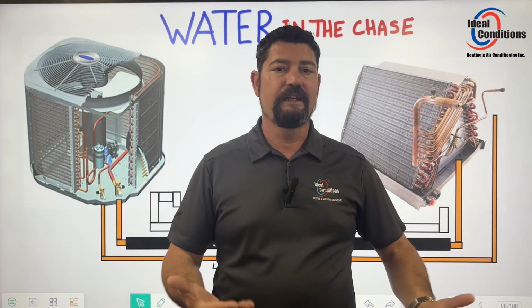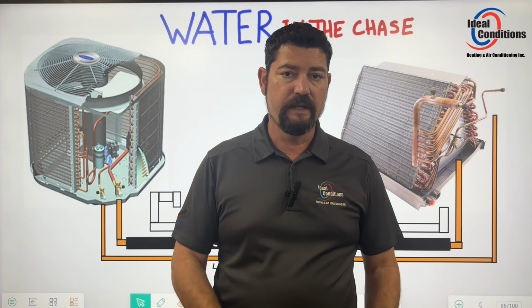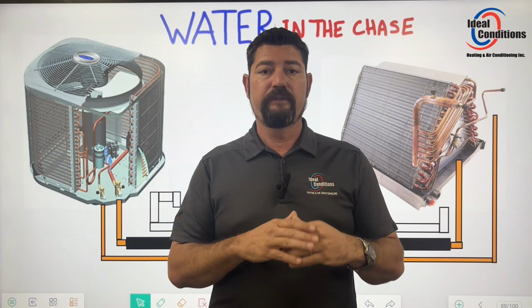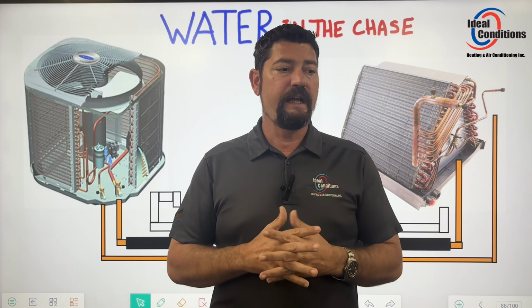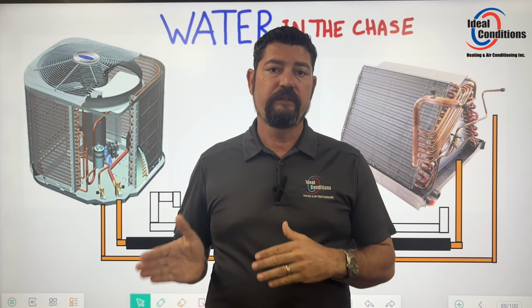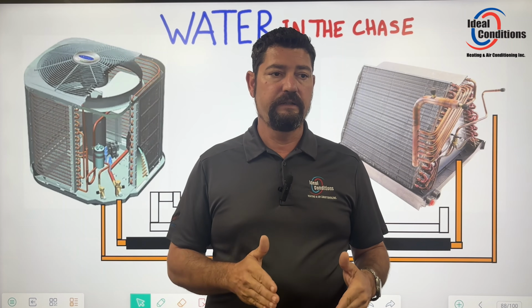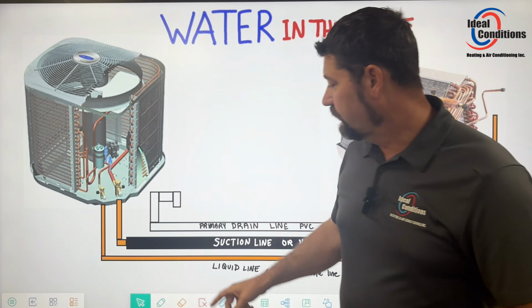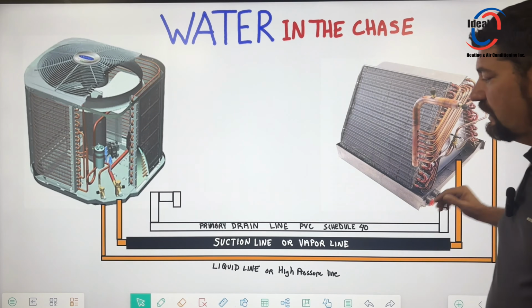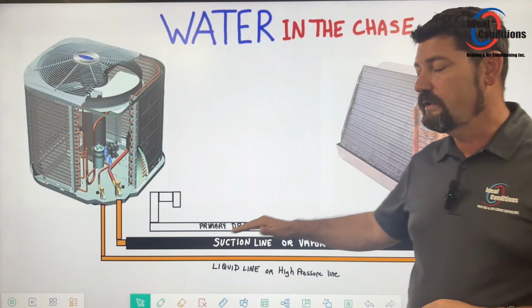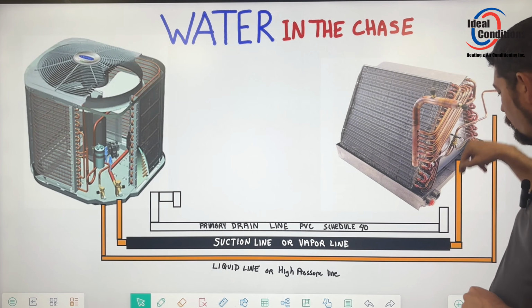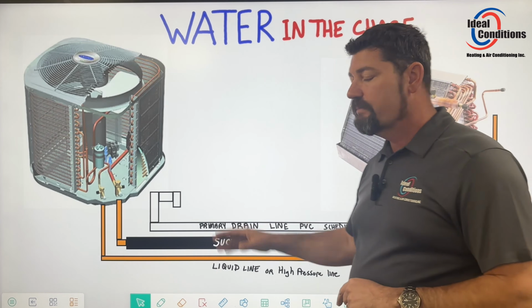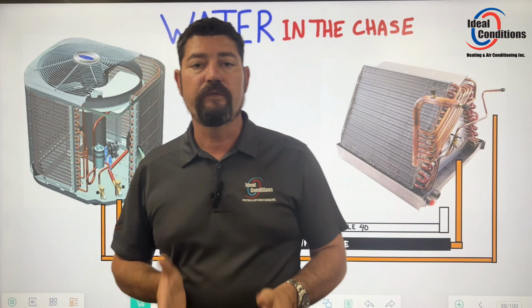But then the next day, or the following morning, you go back out there, and these numbers are always changing. They shouldn't be changing, right? If I have a well-balanced system operating correctly, and my Armaflex is good to go from point A to point B, and I'm not adding or dropping temperature once it leaves the evaporator coil, then my superheat should still be within the 12 to 18 range.